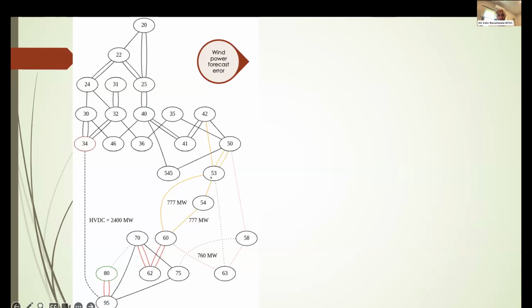Now, we used to have pillars in the middle. There were generators at bus 53, bus 54, bus 60, bus 63. These were thermal generators. But with renewables coming in and with cheaper generation coming in, these are no longer viable. This is where the affordability and the economic dispatch sort of runs into problems. So we had this 1,200 kilometer corridor, an extremely long roof without any pillars in the middle.